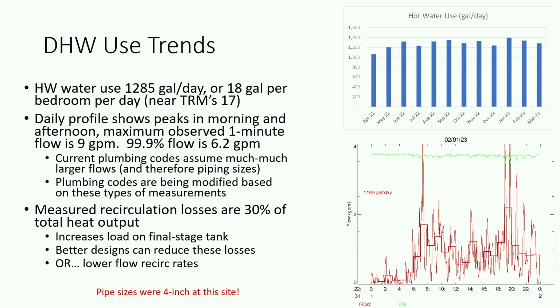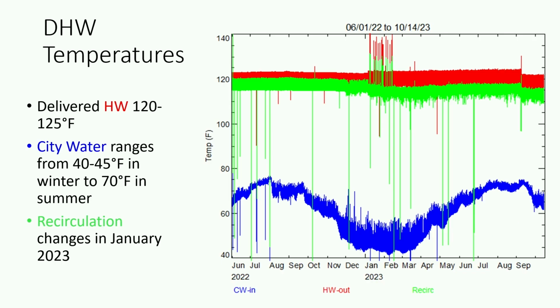And this is not just losses from the recirculation line, it's also disruption to the tank thermoclines and stratification and things like that. And the recirculation line is what made the final tank so hot, because you always have 110-degree water flowing in at about 10 GPM. And because of the guidance in ASHRAE and other places, the engineers expected, so a 4-inch pipe for 6 gallons a minute is a little bigger than you need. And perhaps, so we've done this on 6 sites now, and we've seen flows on this order, and maybe ASHRAE guidance is 10 times too high, maybe it's 5 times too high, but I think the thing you can conclude is that the guidance is too high, and you don't need to size for some of these trends.